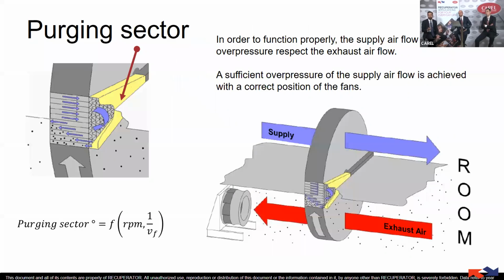So carryover is a problem of contamination, because some of the exhaust air can be trapped inside the rotor, which, while rotating, transports these particles to the supply side. But we can avoid this type of contamination using the purging sector. The purging sector is a panel, the yellow panel you can see, that uses part of the supply air to clean the first channels at the beginning of the supply side. In this way, we have a completely clean matrix rotating inside the supply side, avoiding any type of contamination. For a purging sector to work, it should be installed properly.